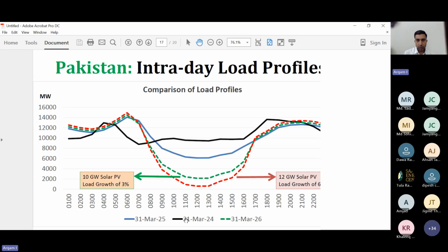As we all know, February and March is the peak production time for solar PV systems. So in March 2024, we did not have much renewable energy or solar PV deployed or up and running in the country. During the early hours, we have around 13,000 megawatt peak demand, and then when the sun starts shining, the solar PV systems start generation, and around 11 a.m. or 12 p.m. the dip was only from 12,000 to 10,000 megawatts. So it is not significant, and the generators in the system capable of ramping down or up, primarily gas turbines and hydro power plants, were able to maintain grid stability.